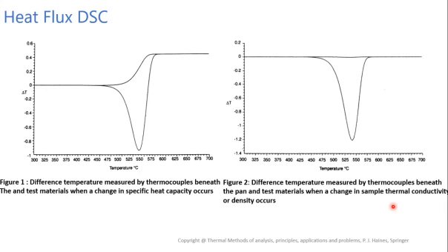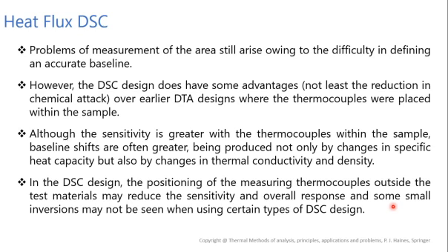Problems of measurement of the area still arise owing to the difficulty in defining the accurate baseline. We have seen in the previous two diagrams that there is a difference in the baseline, and due to that we cannot find the actual peak area, or the area under the peak. However, DSC designs do have some advantages.